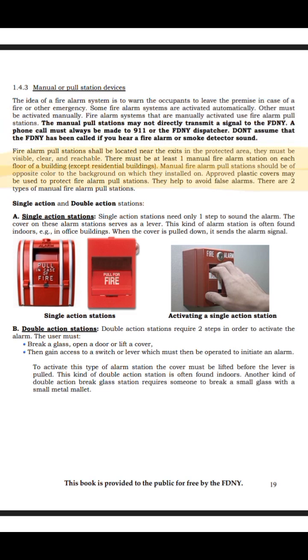Fire alarm pull stations shall be located near the exits in the protected area. They must be visible, clear, and reachable. There must be at least one manual fire alarm station on each floor of a building except residential buildings. Manual fire alarm pull stations should be of opposite color to the background on which they are installed. Approved plastic covers may be used to protect fire alarm pull stations. They help to avoid false alarms.